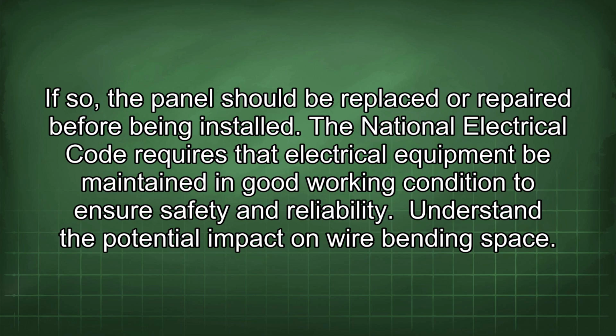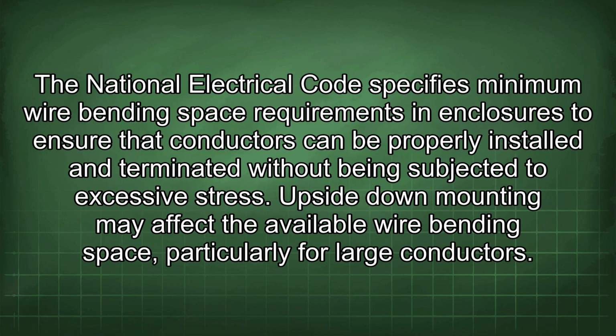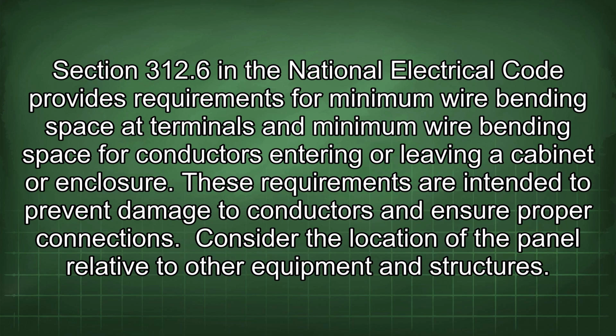Understand the potential impact on wire bending space. The National Electrical Code specifies minimum wire bending space requirements in enclosures to ensure that conductors can be properly installed and terminated without being subjected to excessive stress. Upside-down mounting may affect the available wire bending space, particularly for large conductors. Section 312.6 in the National Electrical Code provides requirements for minimum wire bending space at terminals and minimum wire bending space for conductors entering or leaving a cabinet or enclosure. These requirements are intended to prevent damage to conductors and ensure proper connections.